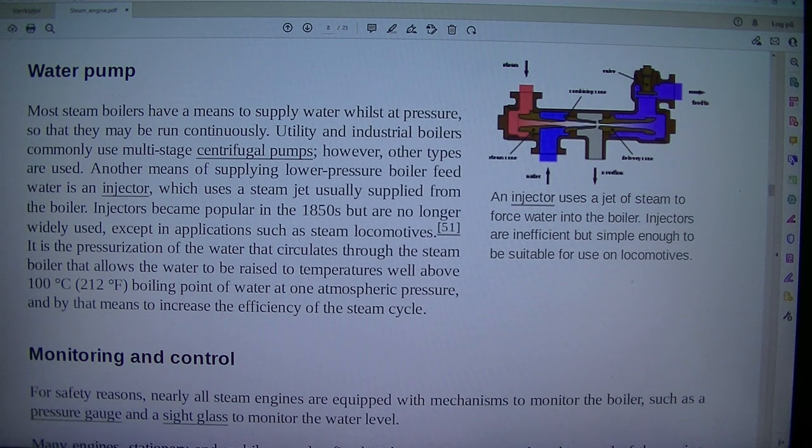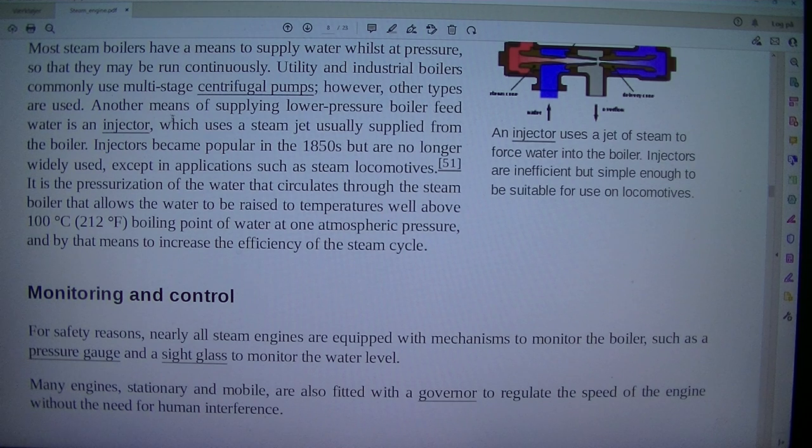Most steam boilers have a means to supply water whilst at pressure so that they may be run continuously. Utility and industrial boilers commonly use multistage centrifugal pumps. However, other types are used. Another means of supplying lower pressure boiler feed water is an injector, which uses a steam jet usually supplied from the boiler. Injectors became popular in the 1850s but are no longer widely used, except in applications such as steam locomotives.